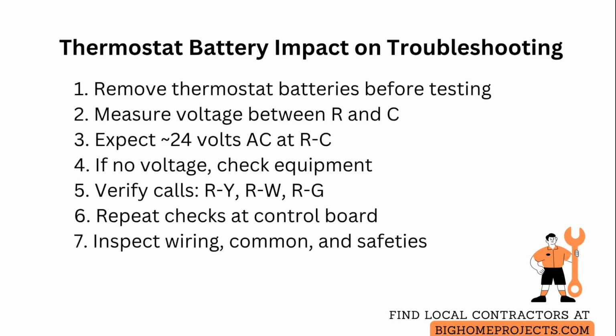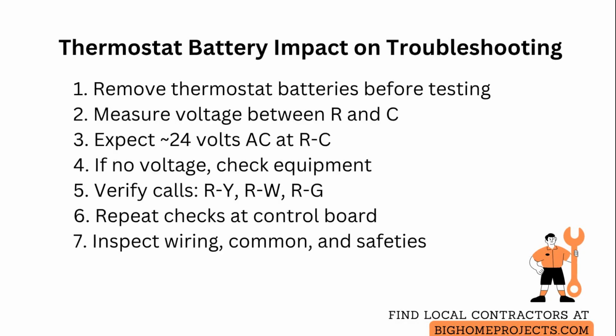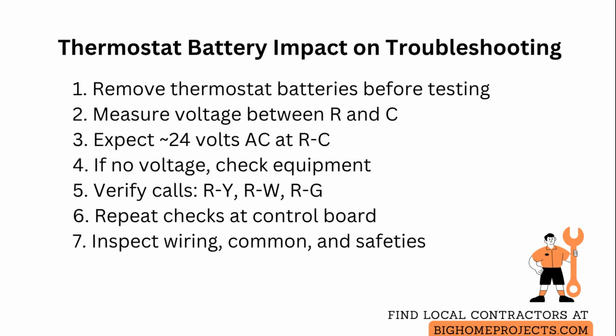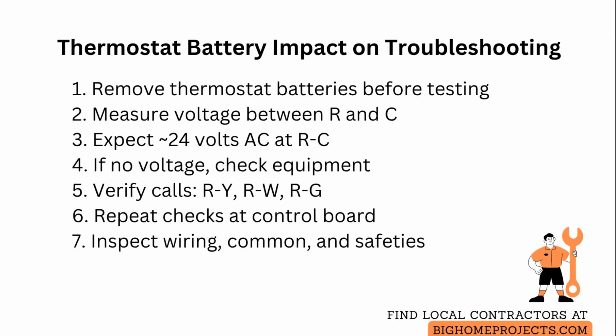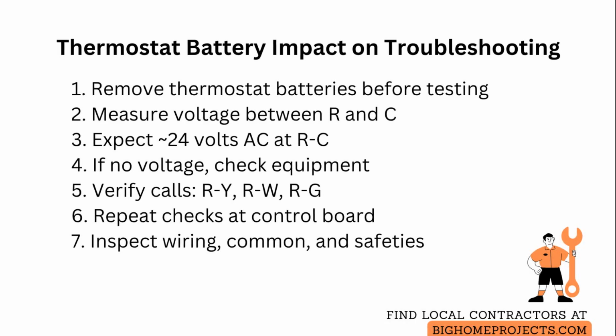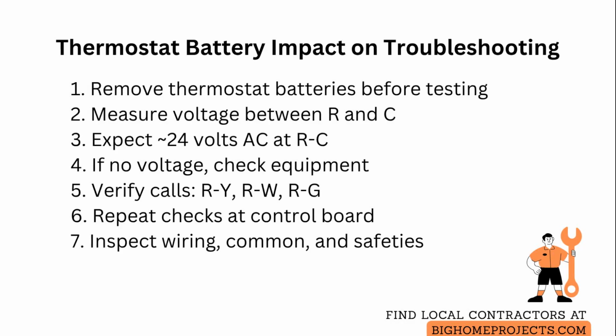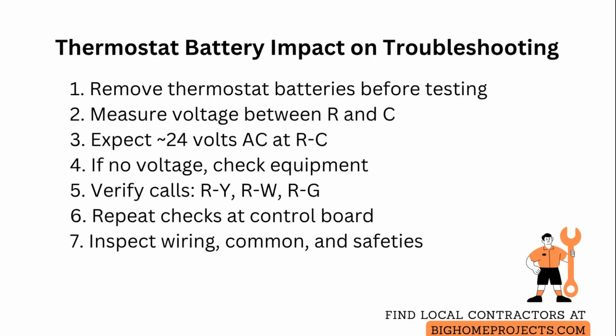a thermostat issue. Start by removing the batteries before any electrical checks, so the display truthfully reflects whether control power is present. With batteries out, measure voltage between R and C at the thermostat base using a reliable meter and look for roughly 24 volts alternating current. No reading means you must work backward to the indoor unit to check the low voltage fuse, transformer primary and secondary, and any float or rollout switches.